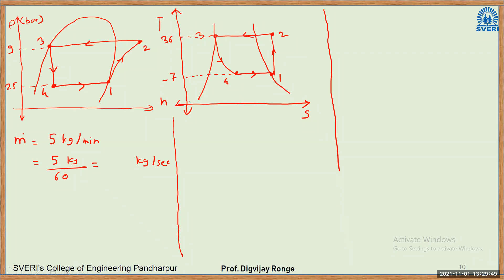Now our main objective is to estimate the theoretical coefficient of performance and also the refrigeration effect. How to calculate the theoretical COP? COP will be equal to refrigeration effect divided by compressor work. So COP is (H1 minus H4) divided by (H2 minus H1). H1 lies on the saturated vapor curve, which is already given in the data, the enthalpy of dry saturated vapor. Now H4: H4 will be equal to H3 because 3 to 4 is an isenthalpic process, and point 3 lies on the saturated liquid curve. That is also given, the enthalpy of saturated liquid at 9 bar. So H1 and H4 can be calculated easily. The main task is to calculate H2, which will take some time.